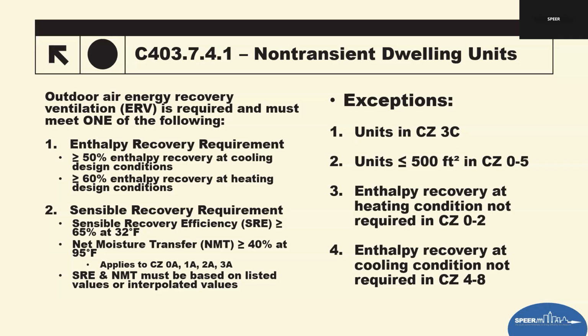The ERVs significantly reduce the energy penalty associated with bringing in outdoor air. This requirement ensures that multifamily residential units inside commercial buildings maintain good ventilation while also reducing heating and cooling loads. So on the plan review tips, confirm each unit qualifies as a non-transient dwelling unit. Also check the ERV performance meets either the enthalpy or the SRE and NMT path. We can go into more of that if you want, or have a call with me on that. We can go through that.